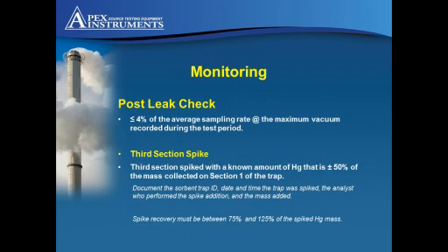Important for the quality control aspect of the sample run, the trap IDs must be recorded. The system software actually reminds you about 3 times during the setup of the test run to record the trap identification data into the test file. But as a tester, it is always useful to carry a small notebook and manually record your activities and those trap IDs.